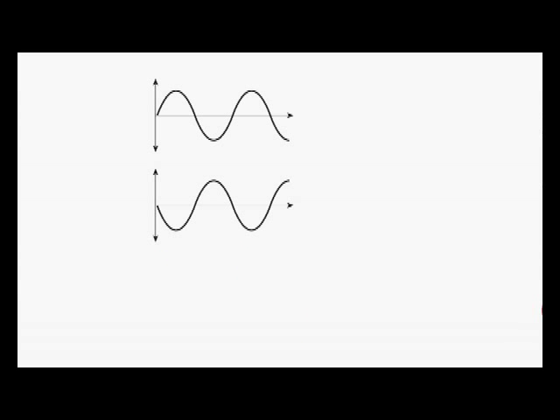If we contrast that with this situation — again two sine waves, but now the first one is heading up when the second one is heading down and vice versa — they're said to be out of phase. If we were to add these two sine waves together, if we're lucky we'd end up with a small sine wave; if we were very unlucky we'd end up with something that was just flat. We've added one plus one to get zero, and that's typically a bad thing in a grid tie situation.